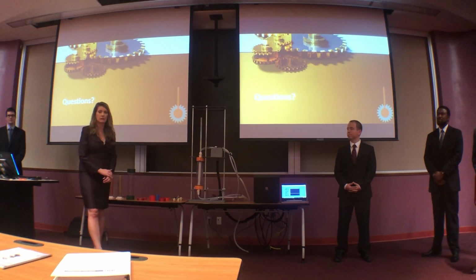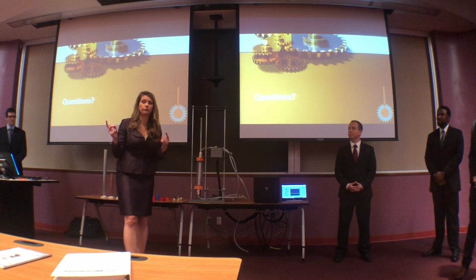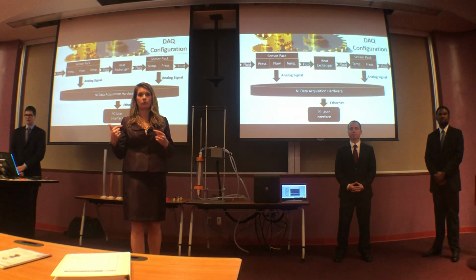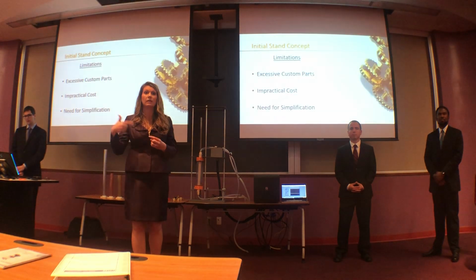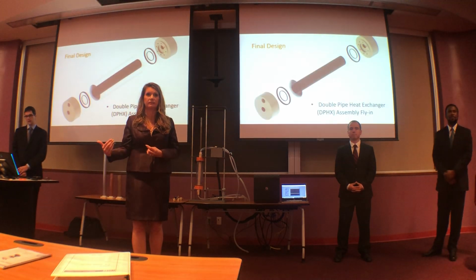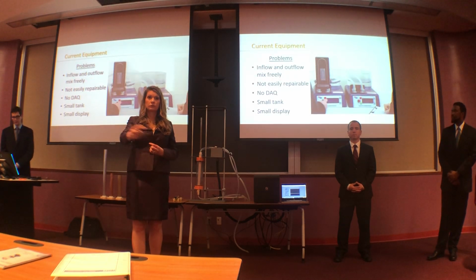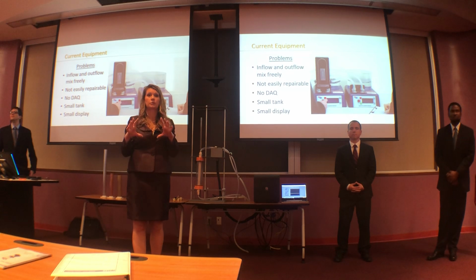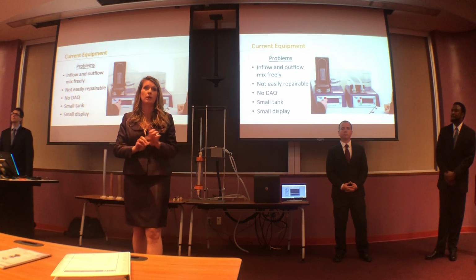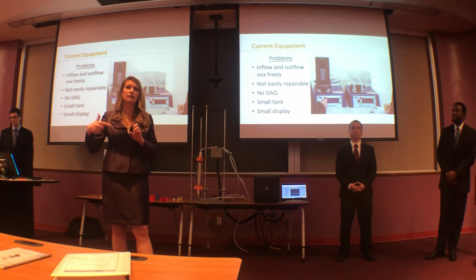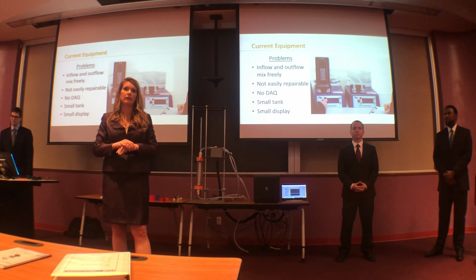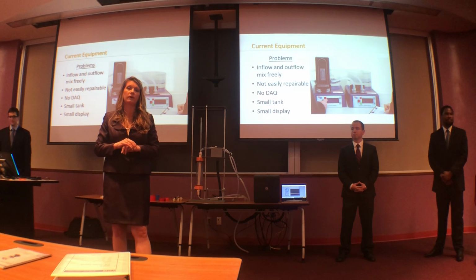The problem statement was that the two fluids mix after time, so you don't keep them separate. The hot fluid eventually mixes with the cold fluid, so the inlet fluid is actually getting warmer. It doesn't stay consistent in the existing units. Because it's a cartridge, as soon as it goes through the heat exchanger, it's actually going back in there, and so then there's mixing going on. It's very short, as far as analyzing the whole overall process.